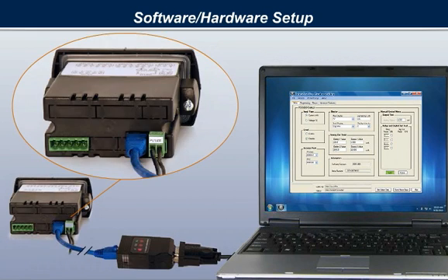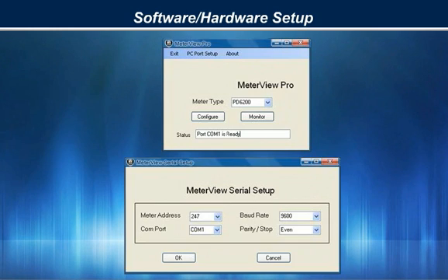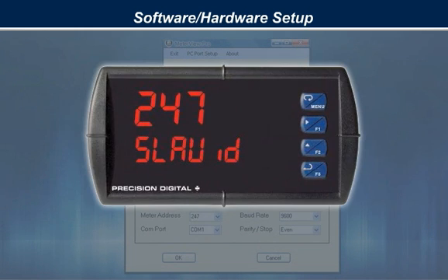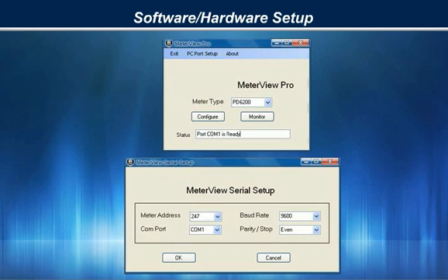Once the easy-to-install communications adapters are connected to the PC, you can start the program. To allow the software to talk to your ProVu meter, simply match the communications settings to that of the ProVu meter, including meter type, address, baud rate, and parity. All of these parameters are easily checked or changed through the meter itself, but the program becomes configured to connect to the default serial settings of your meter. Once the serial adapters are connected and the parameters are matched, just hit either the configure or monitor buttons to begin working with your ProVu meter through MeterView Pro.